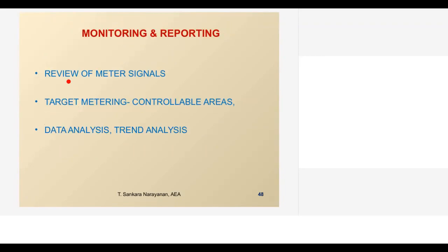In metering also, many times we have seen the meter is calibrated, or they put a sticker saying due for next calibration, but the meter may not be working even though it is calibrated. Once you calibrate the meter, you should also review the signal, especially for a digital meter. If the phase sequence is changed between CT and PT, it will not give proper reading. So we have to review whether all the signals are available on whichever meter has an issue. Even if the phase sequence is changed, it should get reflected in your monitoring system. Otherwise, one particular load will report only one third of its energy. These things we have to review.